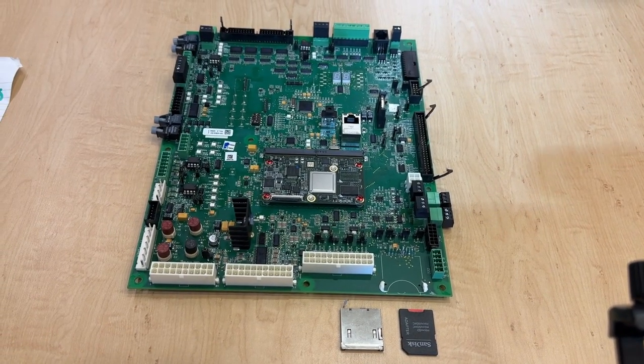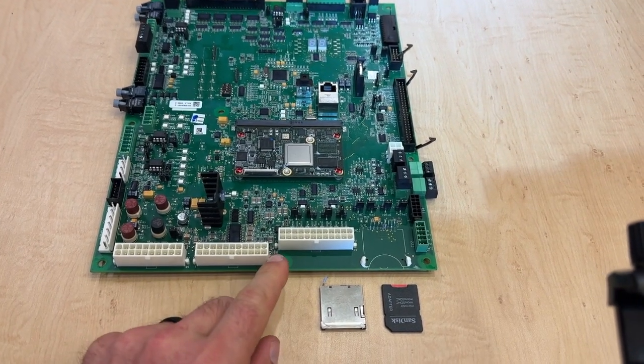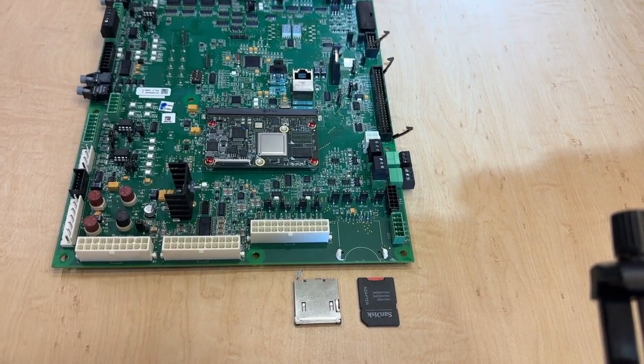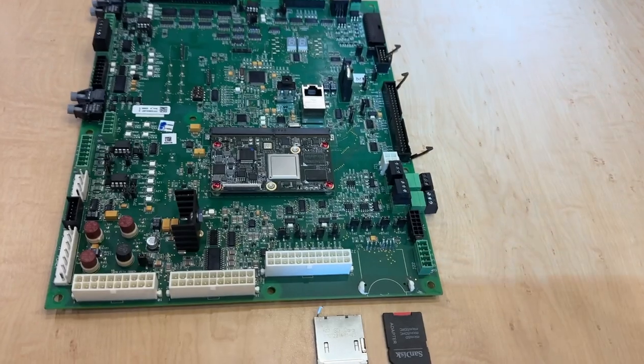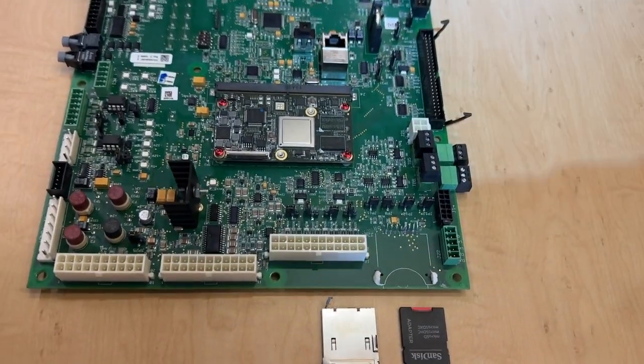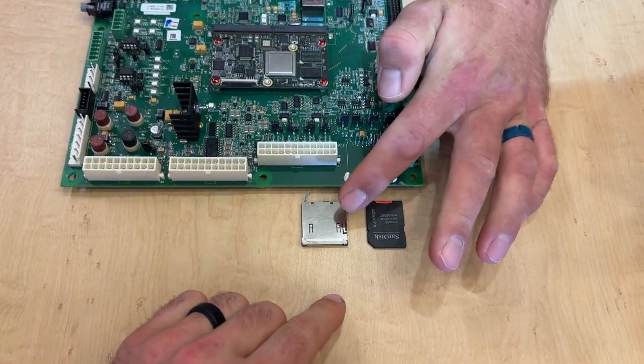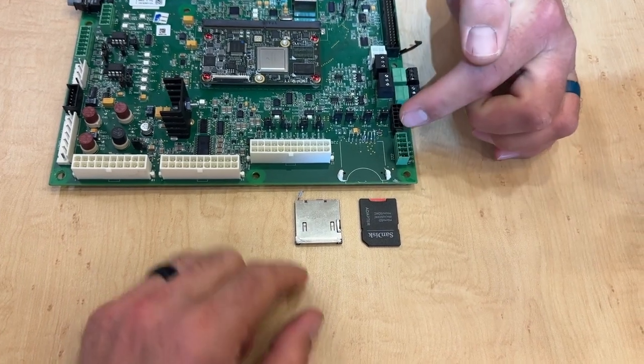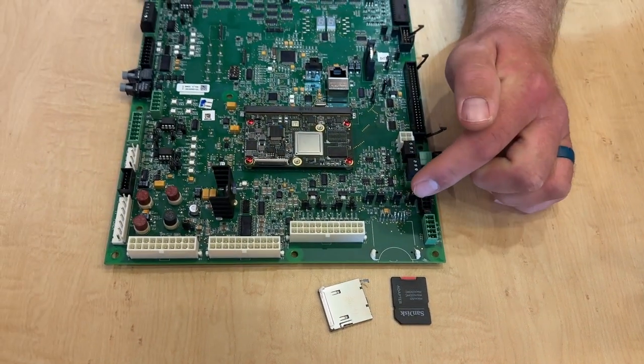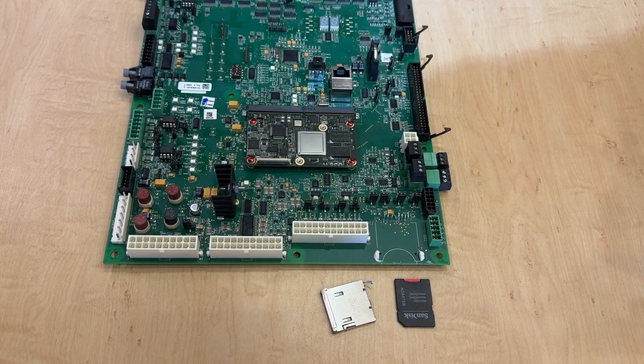There was no audio in that first clip because it's just so loud in that mechanical room. Here's the chiller board — I'm with our chiller tech Matt, and I'm going to let him explain the situation. Essentially what's happened is somebody has pulled the SD card reader off of the board. The SD card reader is used for data logging on the chiller, and also to program the chiller, set programs, and monitor the whole thing if you have issues.